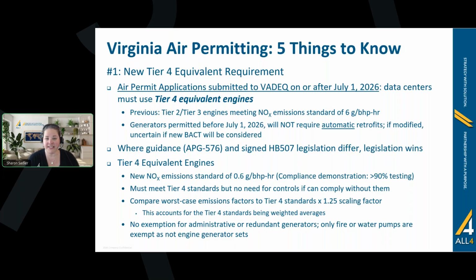This is different from what Virginia has historically required for emergency generators. Their hourly number was 6 grams per brake horsepower hour, and that's what most folks have been working towards. But this is going to be a shift, and if you're sitting there thinking, well, I already have a permit, I already have generators that are permitted or installed, what happens?